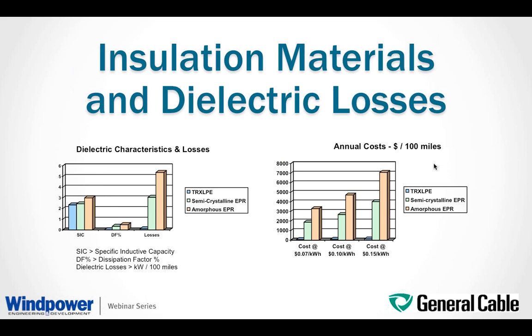Here's just another, a little bit more graphical, way of looking at the comparison between dielectric characteristics and losses of the different types of insulation material. These losses, in the second graph to the right, are translated into annual costs in dollars per 100 miles of cable, calculated for different rates. So again, it shows at a glance the advantage of using TRXLPE insulation to reduce the electric losses within the collector system.